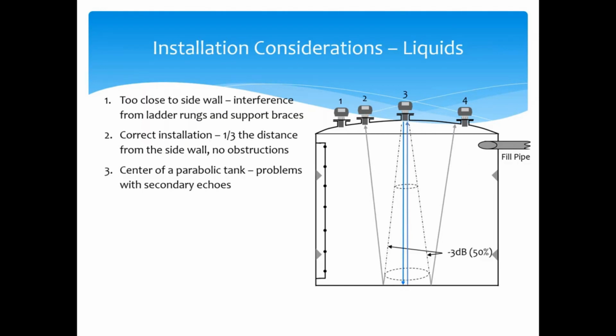Number 3: if this were a flat topped tank, number 3 or number 2 would both work just as well as each other. The reason I brought up the fact that this is a dome top or parabolic tank is that the dome top can actually act like a satellite dish when you're mounted in the dead center. So what that means is we'll get a signal return from our liquid level, wherever it happens to be down here, and then we'll get a secondary signal return after the signal bounces off the top of the tank, comes back down, and comes back up to the transducer again. When you have a dome top tank like this, those secondary echoes can actually be larger than your primary echo. I have a slide that shows that as well.